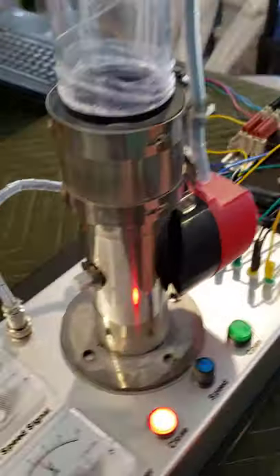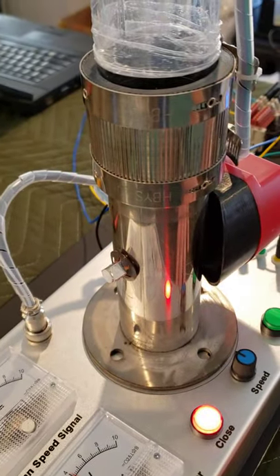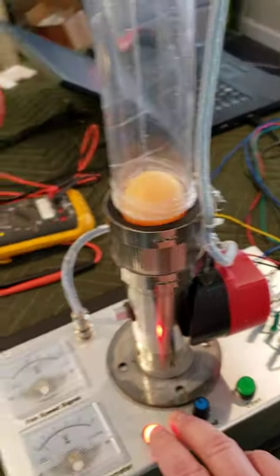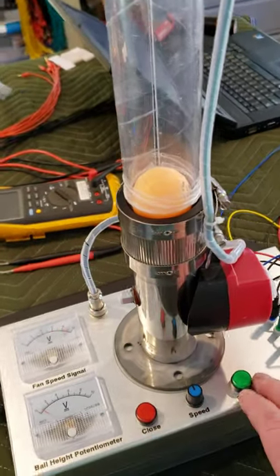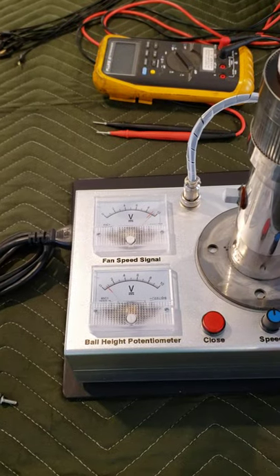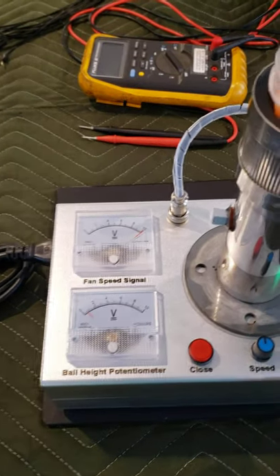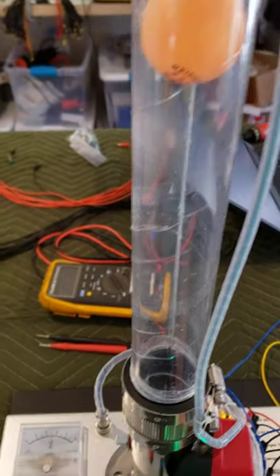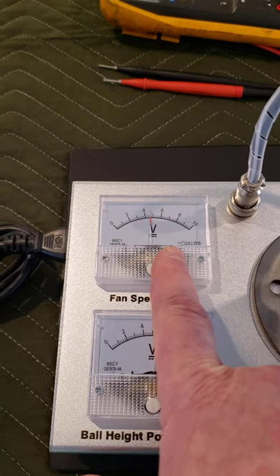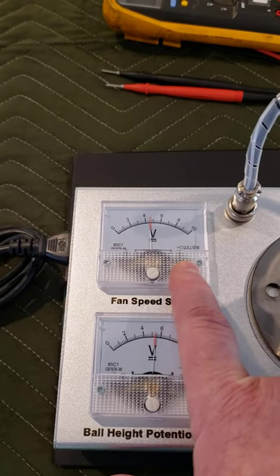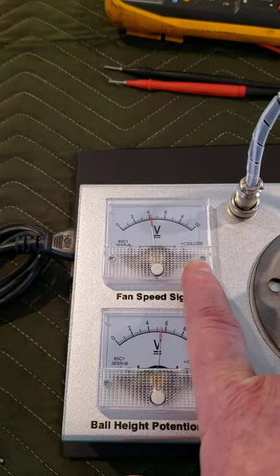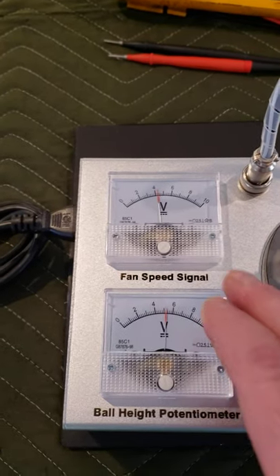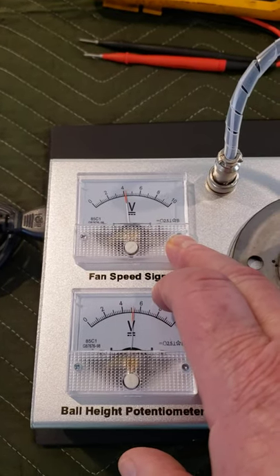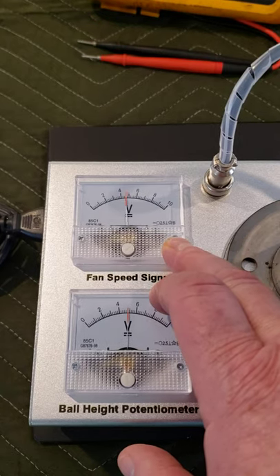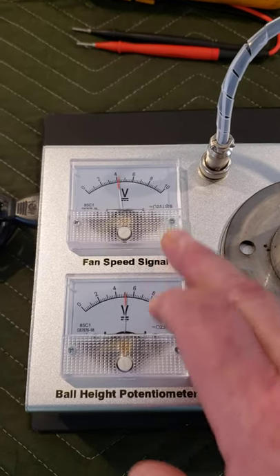These are your open and close. So as the damper closes, the fan's going to try and speed up. And depending upon your PID that you have set, then this is it coming from the controller, from the PLC, or from any kind of analog 0 to 10 volt signal that's coming in to the PID trainer.